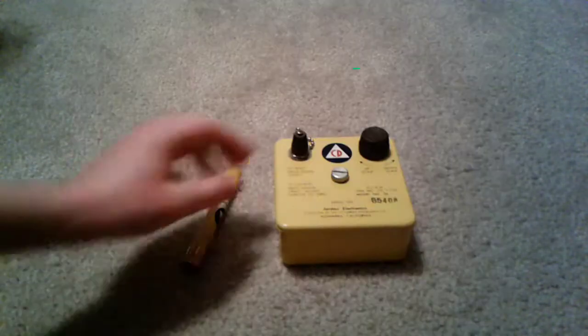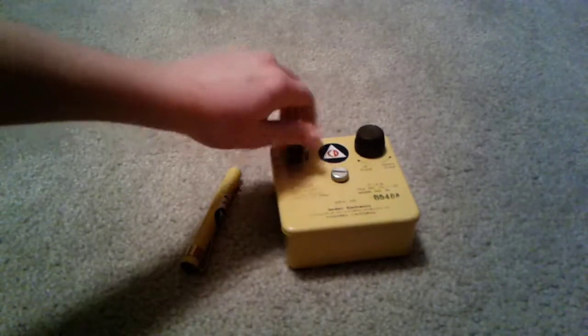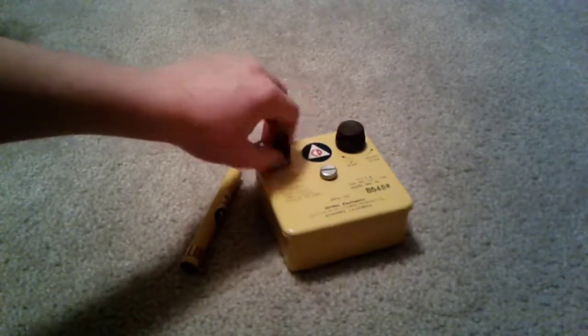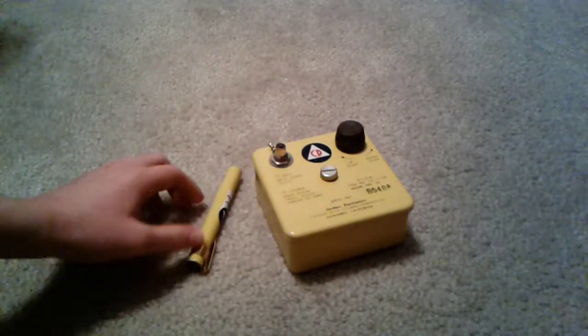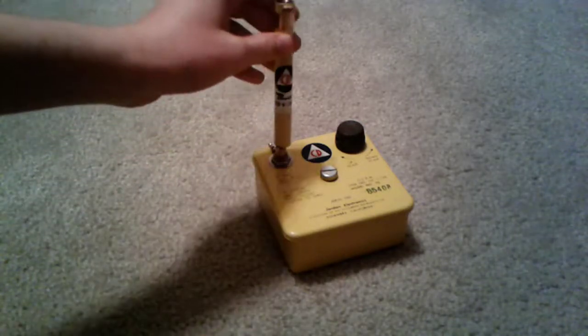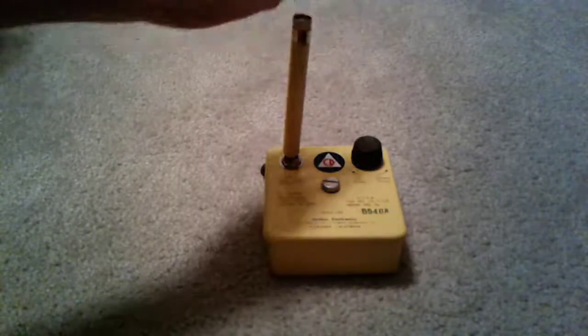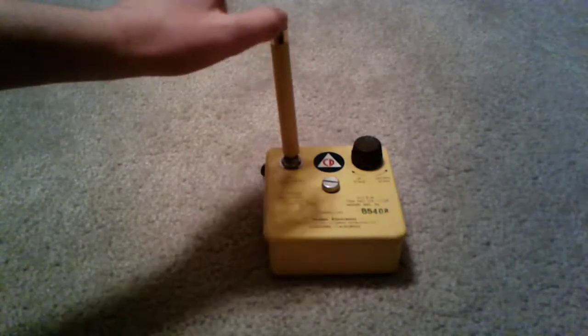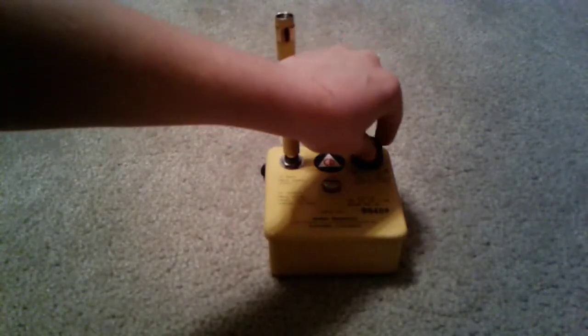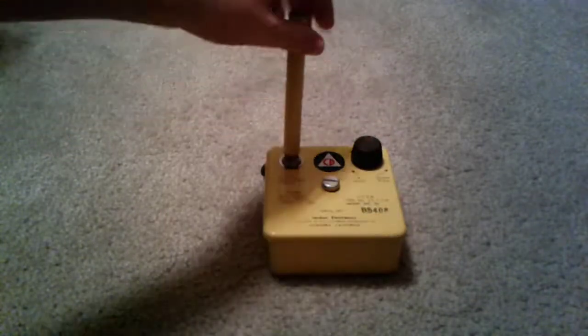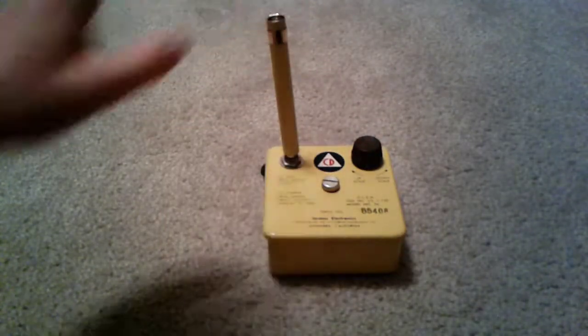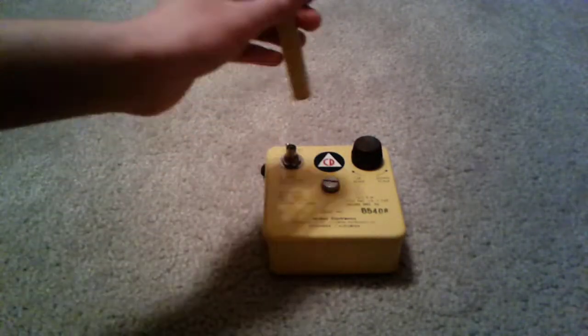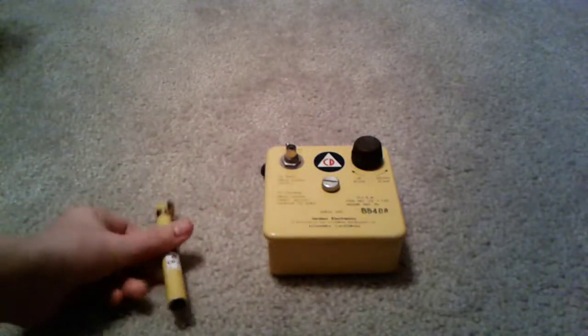Now what you'd do is you'd unscrew the protective cover from the case, and then you'd just put this on, press down until you see the light through this, and you'd look here, and then you'd adjust this knob until the hairline is on zero. And then your dosimeter would be charged and ready to go.